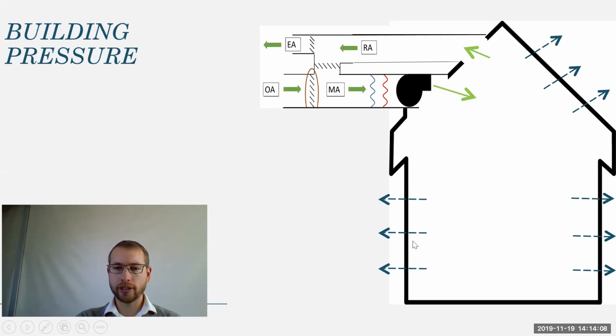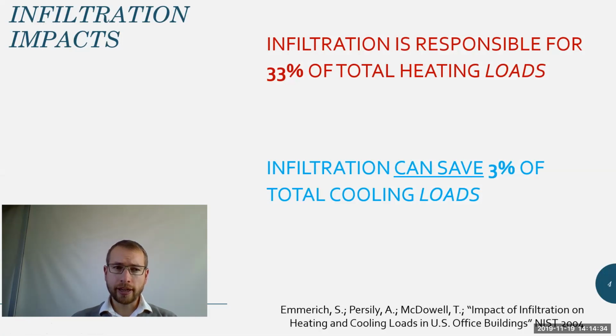So if you open up a door or a window, you should actually be able to feel some of that air kind of pushing out a little bit against you as you walk into the space. And this is really to help reduce infiltration, because if it was underpressurized, all that outdoor air would be trying to find its way into the building, causing really cold or hot spots within the space. And infiltration impacts the HVAC loads quite a bit. It can be up to 30% or more of total heating loads, whereas it can actually save a little bit on total cooling loads. Now, this depends a lot on building and climate.